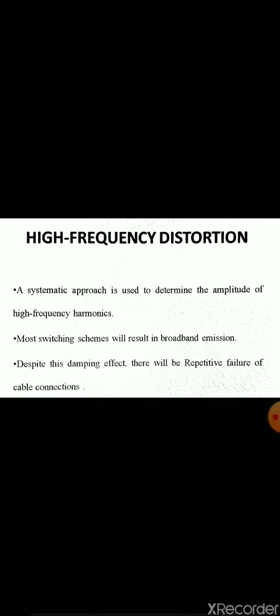Despite this damping effect, repetitive failure of cable connections has been reported due to high distortion in the kilohertz range. The high voltage distortion in that case is due to resonance in the cable connection, which is close to the switching frequency of a power electronics converter connected at medium voltage. So this is regarding high frequency distortion.